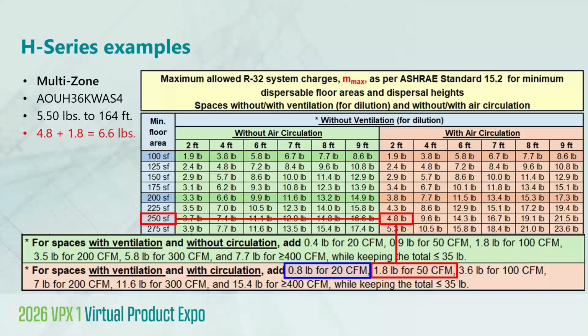So an important detail about the standard is that it specifies the required ventilation CFM, not a fixed number of air exchanges, meaning exhaust air is not necessarily required. And this is where the solution comes together. So as you can see in the inset there on the bottom, red rectangle, that adding just 50 CFM of ventilation air operating in conjunction with circulation, now our maximum allowable refrigerant charge is increased to 6.6 pounds.